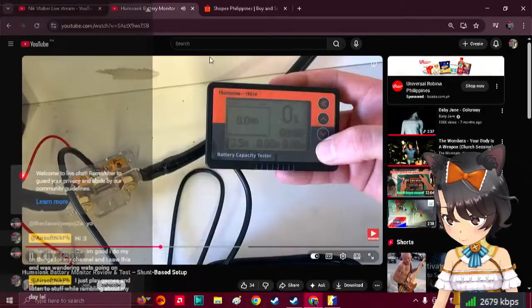Hold the OK button to go in, swap here, and set your alarms. If you're using lead acid, you set your alarm to about 50%. For a 100 amp hour battery, that would be 50. So I went ahead and set it up by long pressing the OK button, and I set my capacity to 100 amp hours.